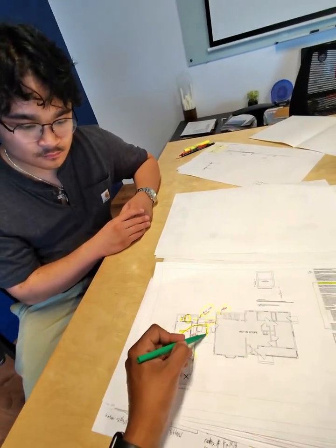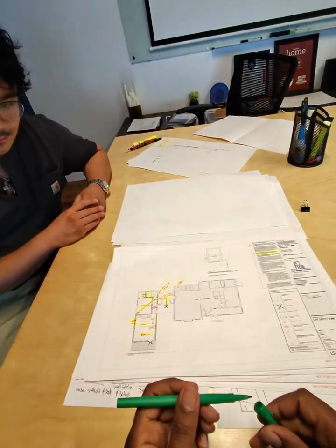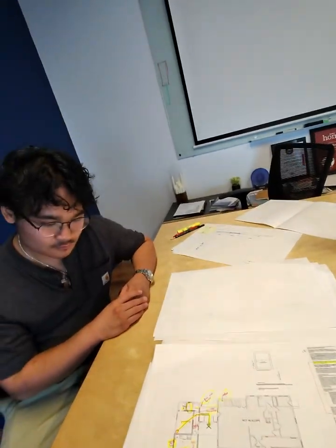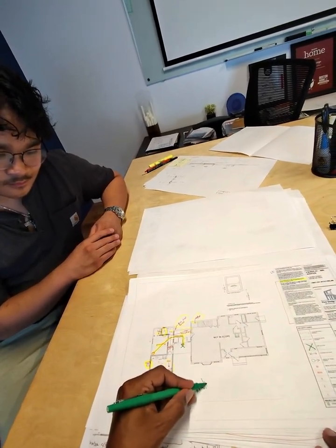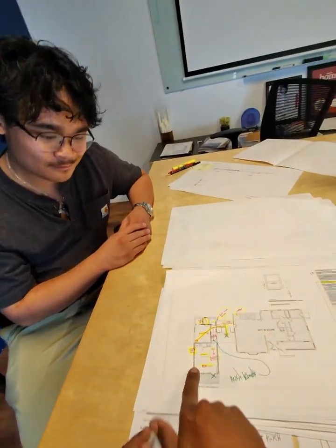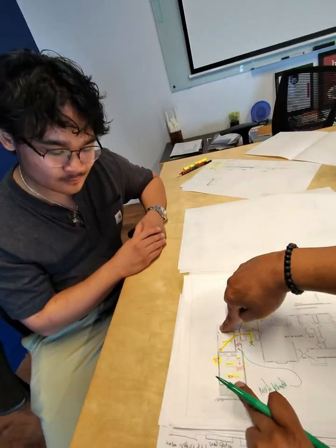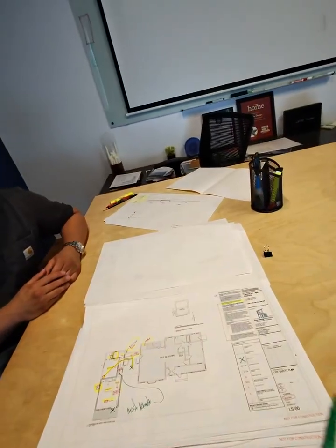One of the most important lines on any project is how you get out of a building. Right, so make sure those lines are good. The egress travel is typically from the most remote location. So you always pick the most remote location, because if you can get out of the most difficult corner, you can get out from the easy corner. So I would pick a corner from here to there, or a corner from here to there, and do the distance. Very important. I don't want you to do things just because I'm telling you to. I want you to do things because you understand why they're done and when they're done and when they're not. That's called judgment.